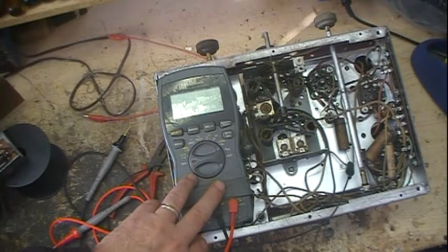But if you're not absolutely sure but you still want to test for it, what you can do is use something like a 10 ohm resistor and put it in circuit. In other words, where you would normally put the meter in the circuit as a current meter, instead put a 10 ohm resistor there, and get one of those 1% 10 ohm resistors. You can even measure it prior to putting it in and write down that exact measurement, but put it in and then you can measure the voltage drop across that resistor, and then do Ohm's law. Voltage divided by resistance gives you current, and that way it gives you a safe way of checking current, not having to worry about how you hook the meter up, or if it's on the right range, or possibly damaging the meter.